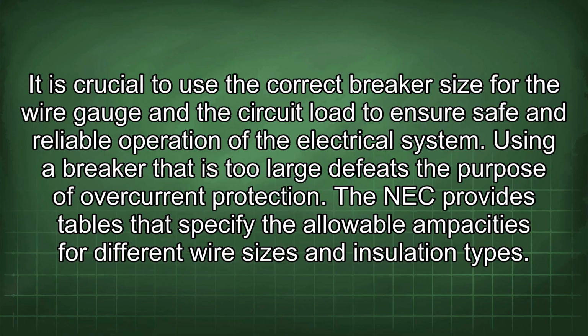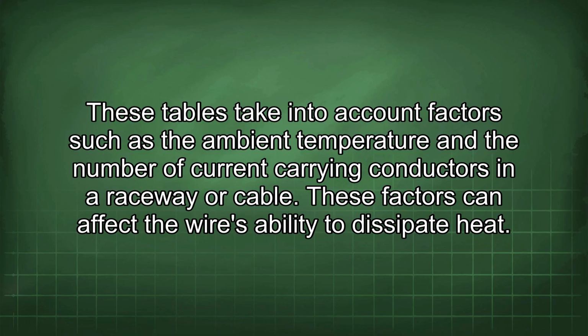Using a breaker that is too large defeats the purpose of overcurrent protection. The NEC provides tables that specify the allowable ampacities for different wire sizes and insulation types. These tables take into account factors such as the ambient temperature and the number of current-carrying conductors in a raceway or cable. These factors can affect the wire's ability to dissipate heat.